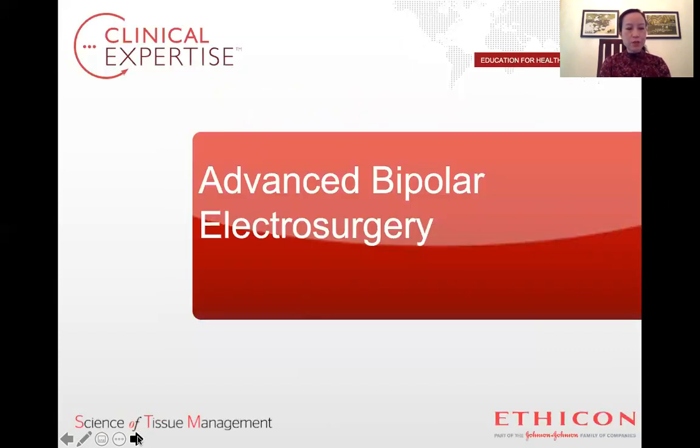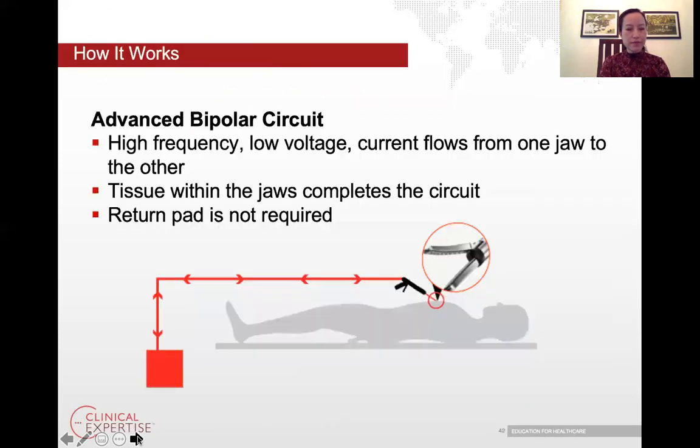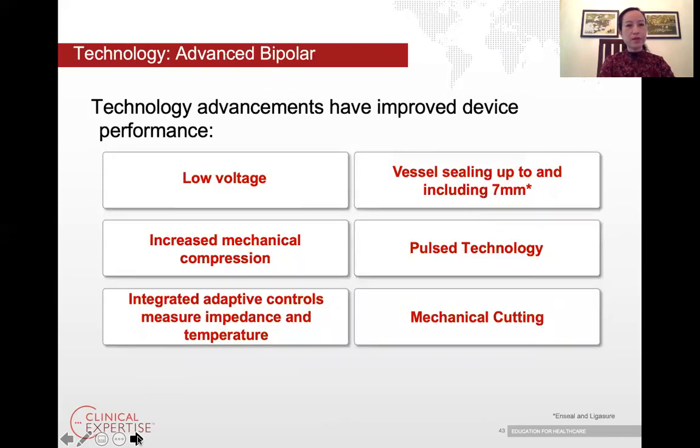Recognition of the limitations of the traditional bipolar modality led to the development of advanced bipolar electrosurgery. The advanced bipolar circuit is similar to the traditional circuit. However, improvements in device performance have been developed, including lower voltage systems and better sealing through better compression, heat, and time management.